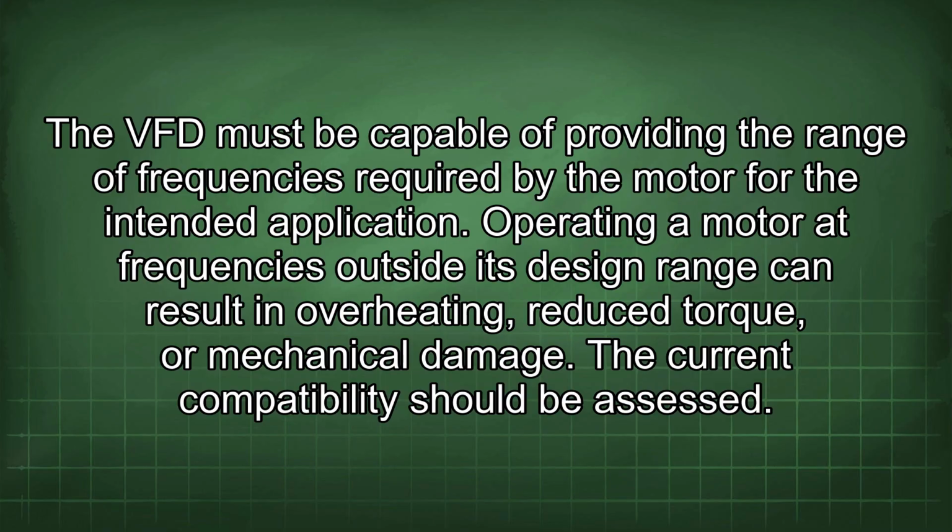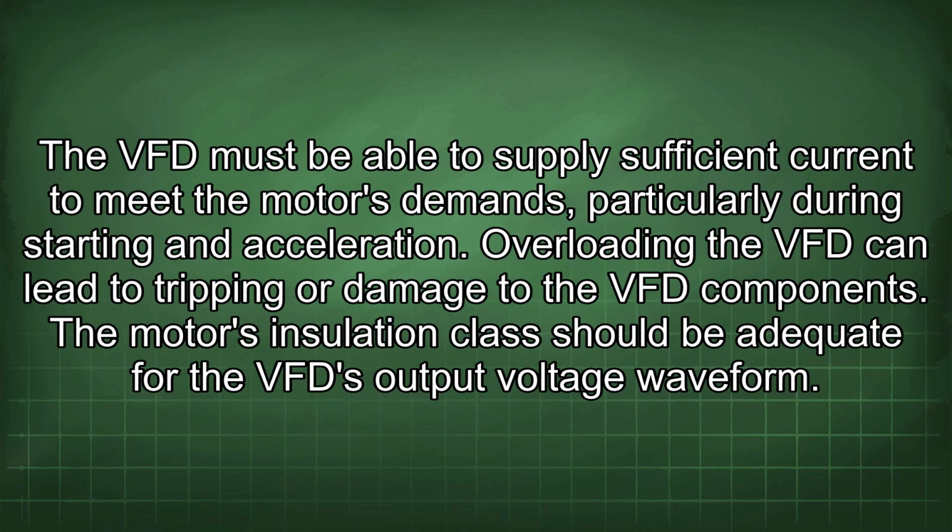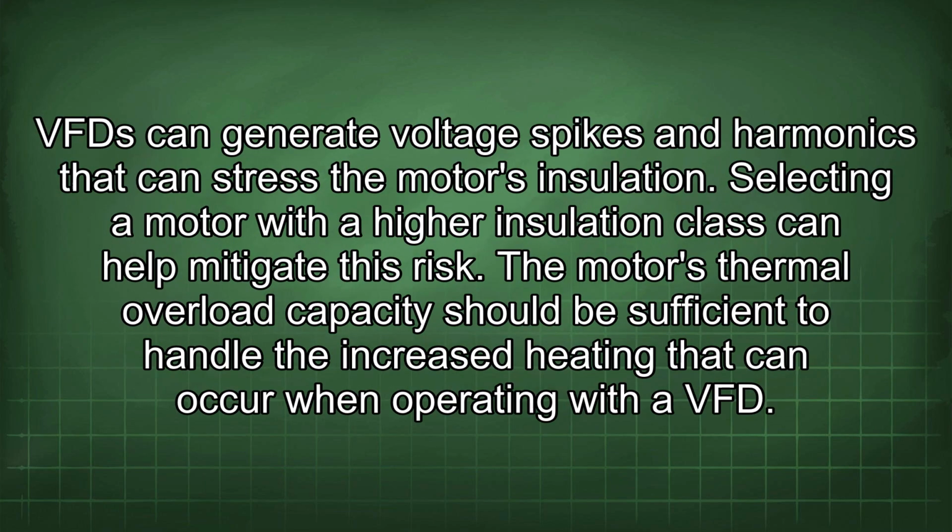The current compatibility should be assessed. The VFD must be able to supply sufficient current to meet the motor's demands, particularly during starting and acceleration. Overloading the VFD can lead to tripping or damage to the VFD components. The motor's insulation class should be adequate for the VFD output voltage waveform. VFDs can generate voltage spikes and harmonics that can stress the motor's insulation. Selecting a motor with a higher insulation class can help mitigate this risk.